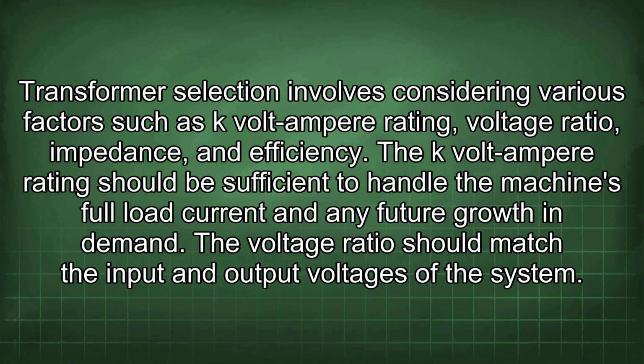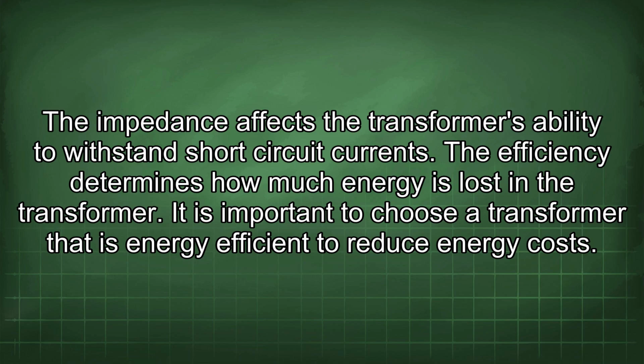Transformer selection involves considering various factors such as kVA rating, voltage ratio, impedance, and efficiency. The kVA rating should be sufficient to handle the machine's full load current and any future growth in demand. The voltage ratio should match the input and output voltages of the system. The impedance affects the transformer's ability to withstand short-circuit currents. The efficiency determines how much energy is lost in the transformer. It is important to choose a transformer that is energy efficient to reduce energy costs.